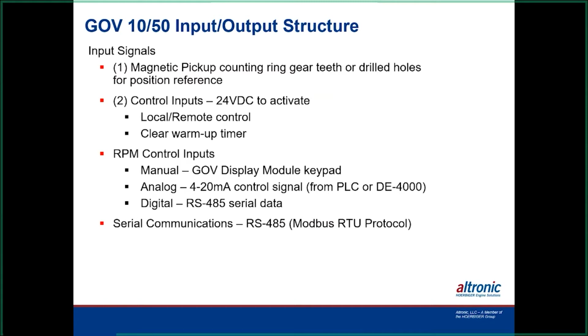Again, we talked about most of this. We require a separate mag pickup. We never recommend tagging another pickup onto this, because this is controlling the speed of the engine, so it needs to have its own pickup. It can either count the ring gear teeth, or you can drill holes in the flywheel and program the device to let it know how many teeth or holes there are. It runs on 24 volts. It can operate the speed either locally or remotely. And then, like I said earlier, you can clear the warm-up timer if you need to get it online in a hurry.